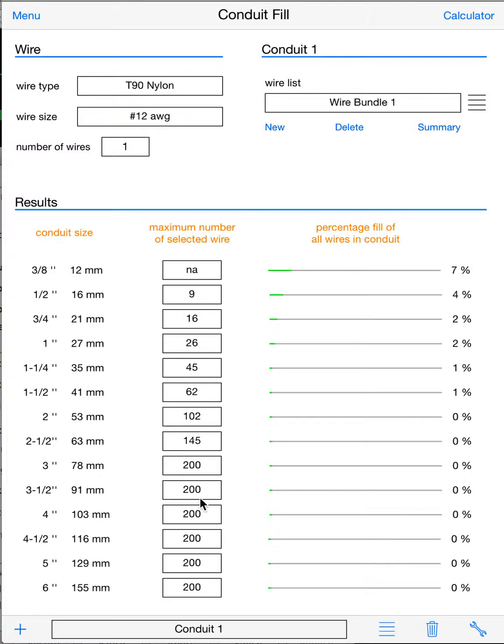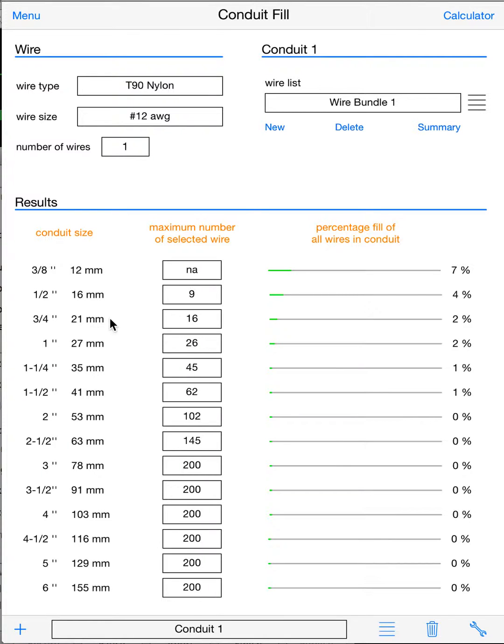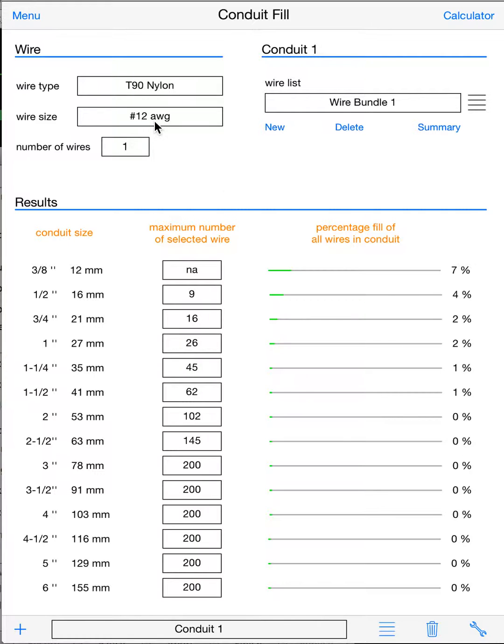You can look at your maximum number of that wire type and size that you can put in each conduit size. So half inch, you can fit 9 number 12 T90s; three-quarter inch, 16 number 12 T90s, etc. And that's it. That'll save you a lot of time going to the code book to find those results.